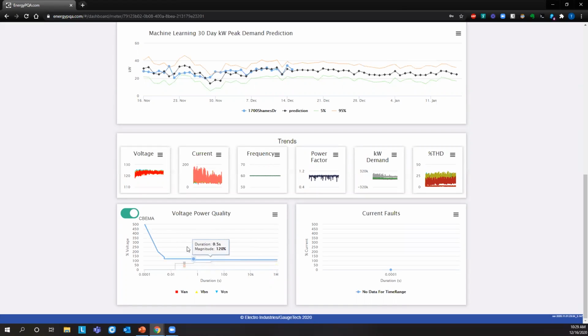Down here we have the power quality, voltage, CBEMA curve, as well as any current faults. So in this case, we've got a couple events. Those of you not familiar with the CBEMA curve, this isn't a hard and fast rule. This is just a guideline. Anything that happens between this blue and black line here are events that pieces of electronic equipment should be able to continue operation through.